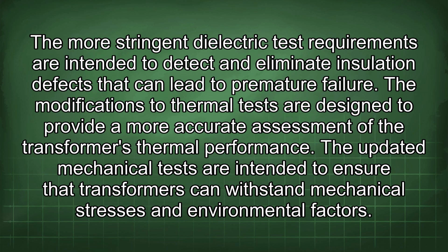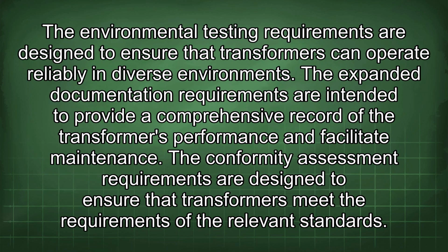The more stringent dielectric test requirements are intended to detect and eliminate insulation defects that can lead to premature failure. The modifications to thermal tests are designed to provide a more accurate assessment of the transformer's thermal performance. The updated mechanical tests are intended to ensure that transformers can withstand mechanical stresses and environmental factors. The environmental testing requirements are designed to ensure that transformers can operate reliably in diverse environments. The expanded documentation requirements are intended to provide a comprehensive record of the transformer's performance and facilitate maintenance. The conformity assessment requirements are designed to ensure that transformers meet the requirements of the relevant standards.